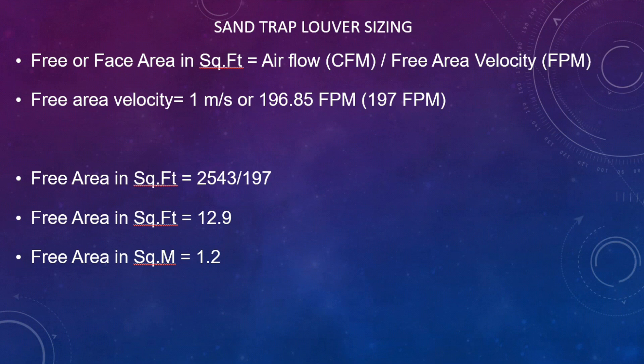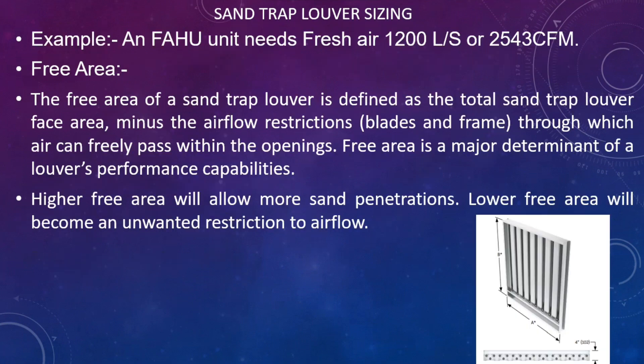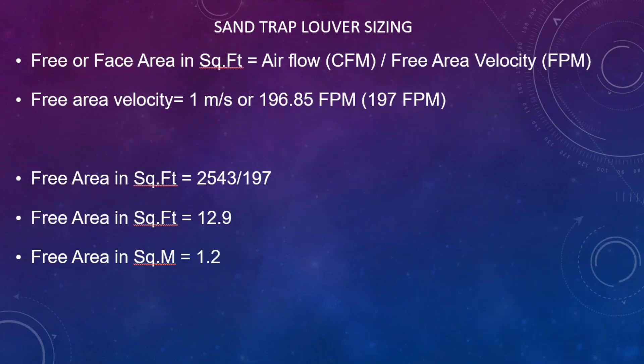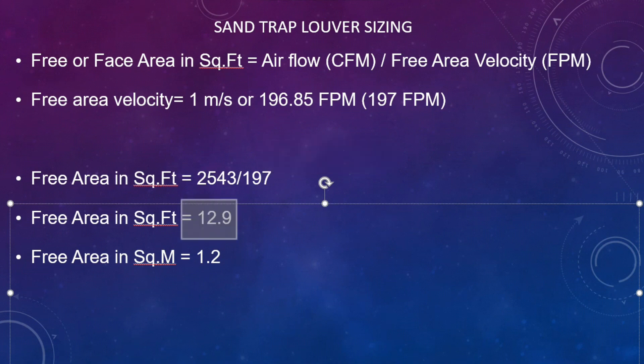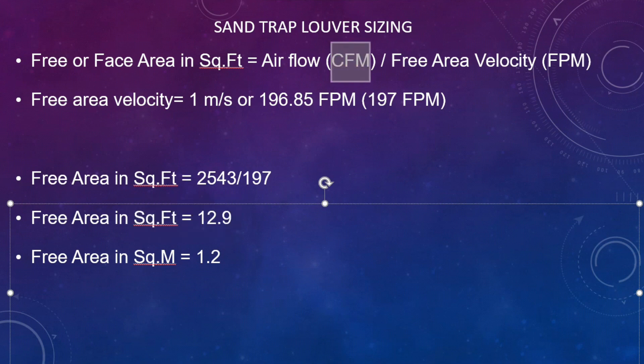The free area velocity is taken as 1 meter per second or 197 feet per minute. Coming to the calculation: free area in square feet equals 2543 CFM — in our case, 1200 liters per second or 2543 CFM — divided by the free area velocity of 197. Finally, we get the answer of 12.9 square feet. Since the units are cubic feet per minute divided by feet per minute, the answer comes in square feet, which we then need to convert to square meters.